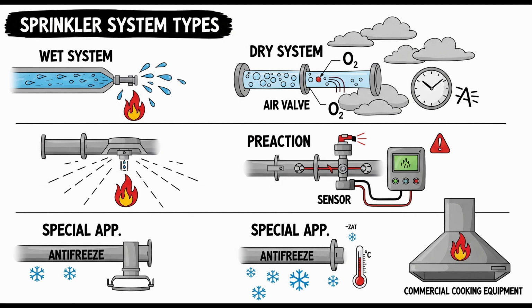Okay. The two valves are cross-connected using a 1-inch pipe. This cross-connection ensures they trip simultaneously when the detection system sends a signal. So the detection signal effectively hits both valves at the same time via that small pipe connection. Right. That 1-inch cross-connection must have an indicating valve in it, which allows one of the two main dry pipe valves to be isolated for maintenance while the other remains in service. This is vital for maintaining at least partial protection on these large critical systems during servicing. Smart design for maintainability without complete shutdown.